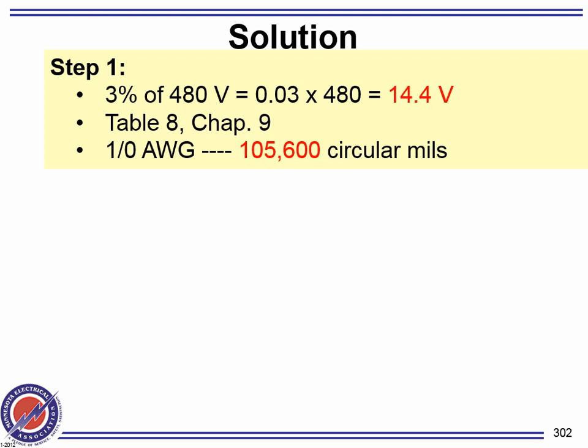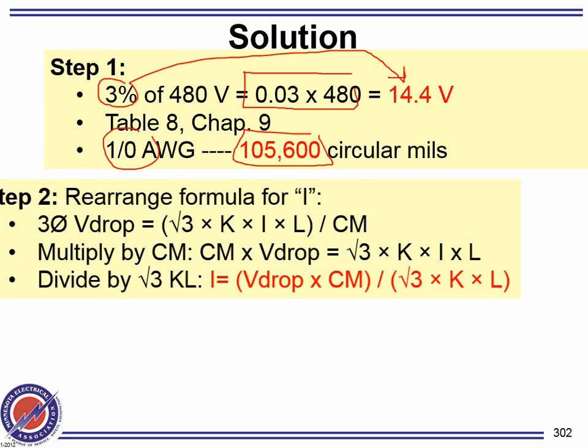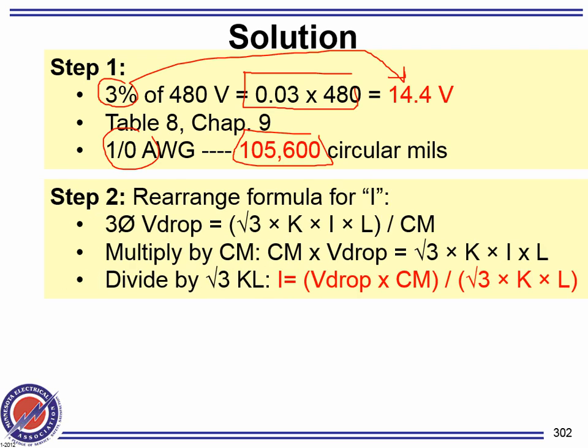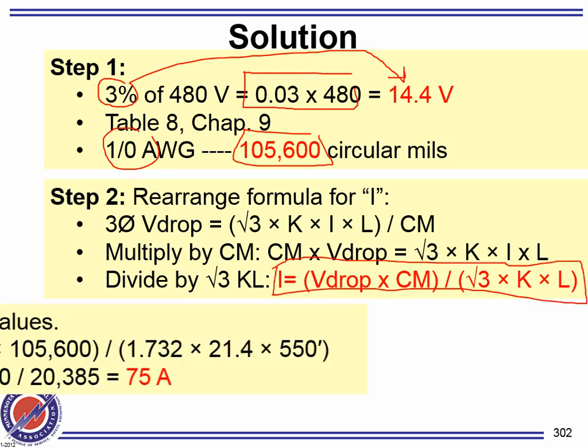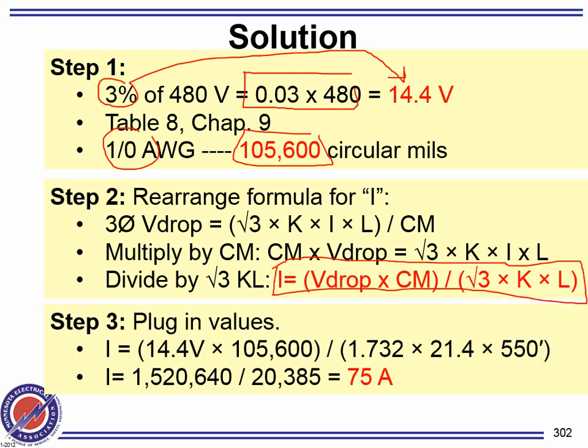Okay, first you need to convert the 3% into actual voltage. That's how you do them. 3% of 480 gives you 14.4. 1/0 translates to this amount of circular mil. Flip the formula, which you guys have done. You and I have done that one. Flipping the formula in the form of an I to get you an I, and then plug them in, and you got yourself a 75 amp.